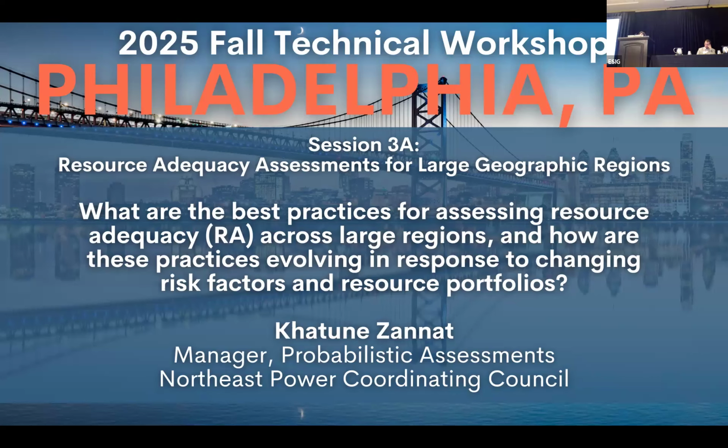So what we are doing at NPCC is, as I mentioned, we have a reliability assessment program where our planning coordinators and areas have to demonstrate each year that they are meeting the loss of load expectation, that disconnecting firm load due to resource deficiencies is on average no more than 1 day in 10 years.